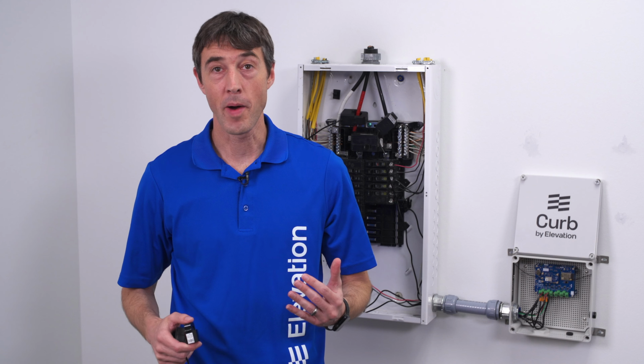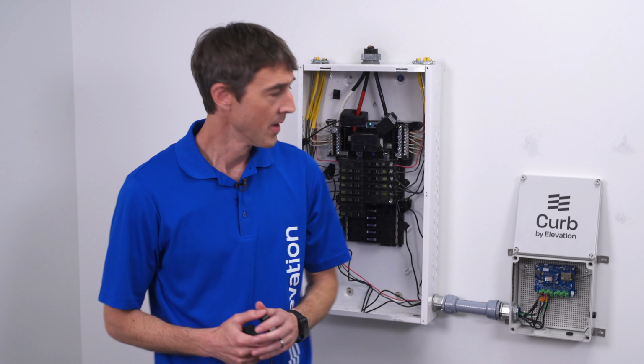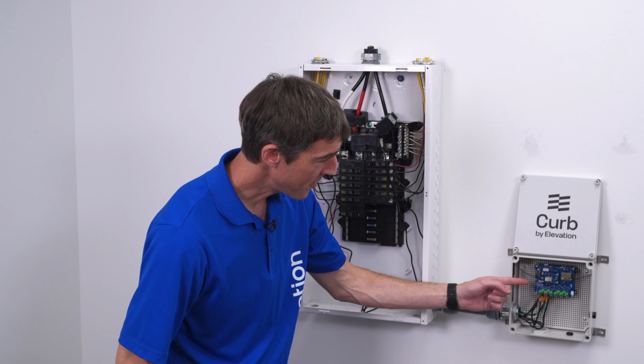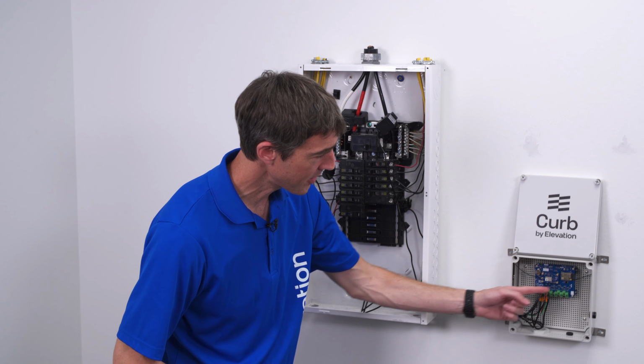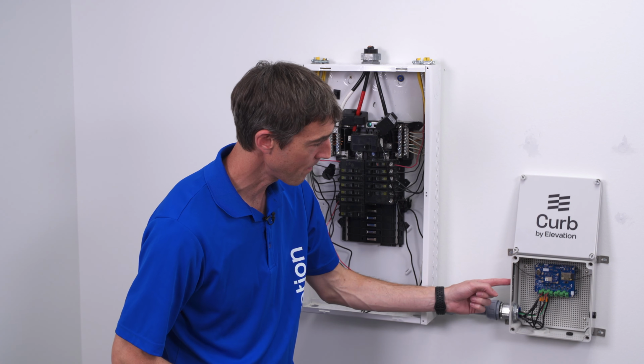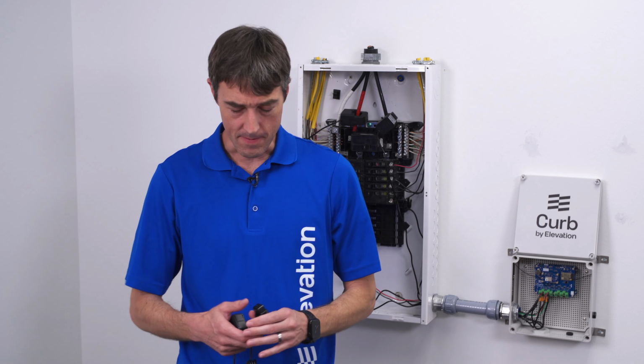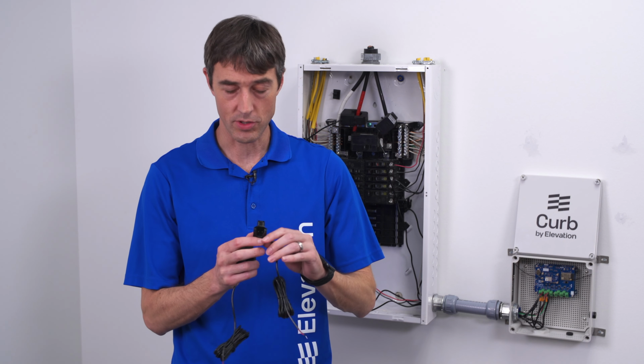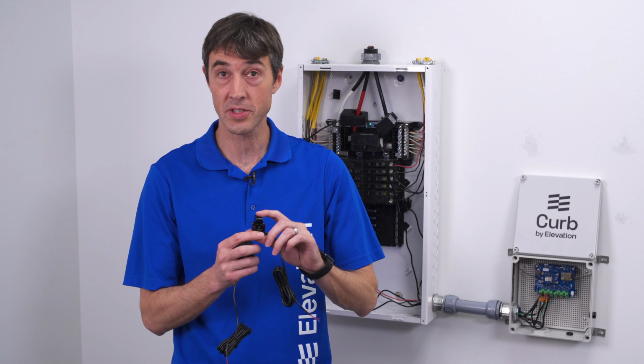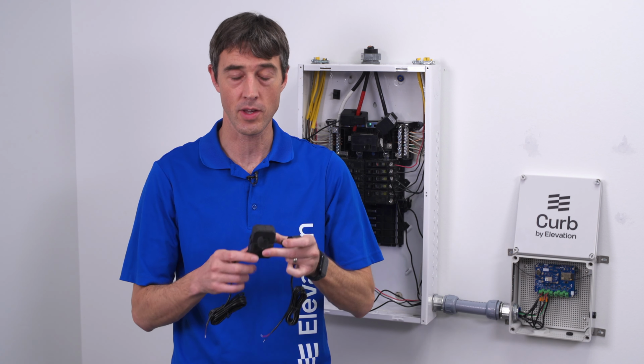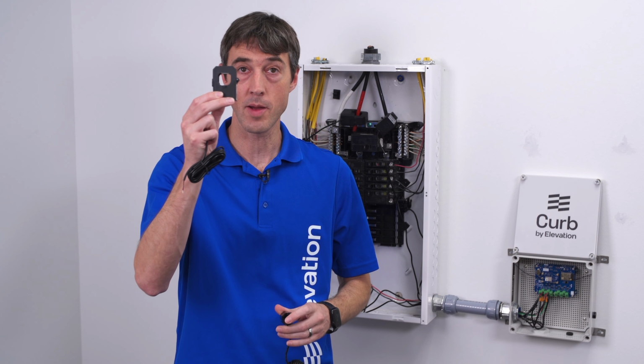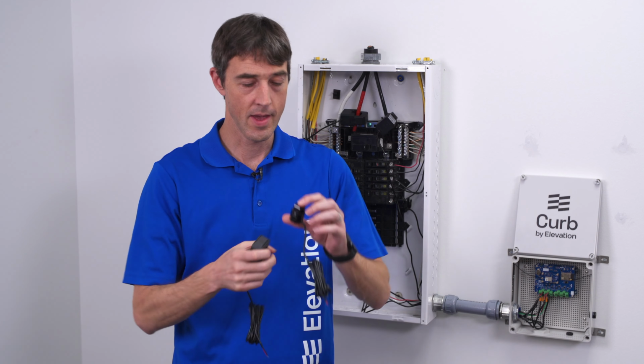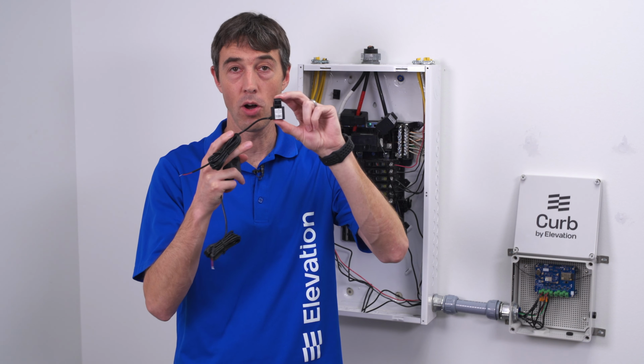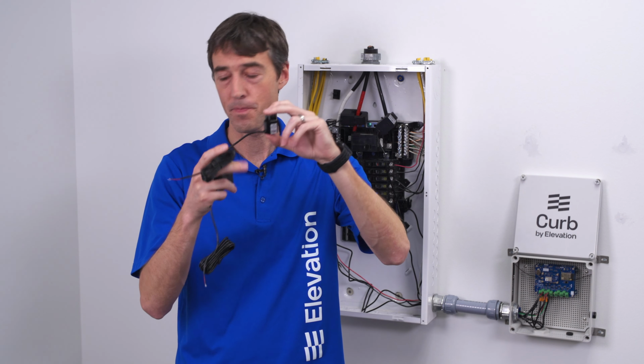Let's get started by getting familiar with the different components that are included in the Curb system. The first part is the Curb M10 device, which is this blue device inside of this enclosure. The second thing to see is the CT clamp sensors. There are 10 total CT clamp sensors, 2 different sizes. First, the large 100 amp CT clamps. There's 2 of those. And then there are 8 smaller 30 amp CT clamps.